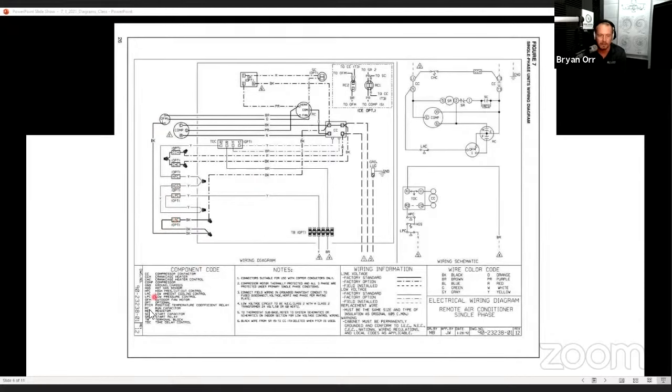All right, I'm gonna zoom out here a little bit. We're gonna look here at this little circuit. This is something that one of the commenters was talking about earlier. Easy heat and cooling was mentioned in this, that there are a lot of series switch circuits, or switches in series, for safety. So we have an LPC, we have an HGS, we have an HPC, right? Low pressure control, hot gas switch, high pressure control. And then we have this time delay circuit. So this is a new one that you haven't seen before. But this little arrow guy is a time delay circuit.